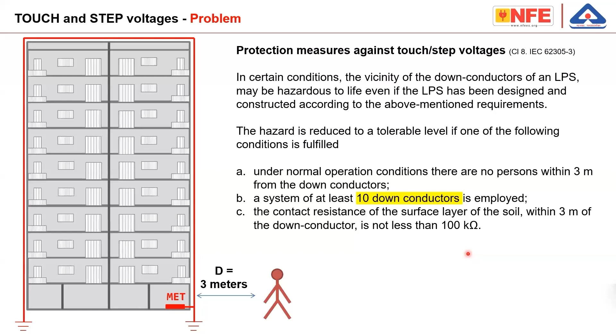Similarly, the step voltages are also mentioned in the standard. In order to avoid touch voltage, what you should do is this: the down conductor, where I am moving the cursor, of that part of the building up to, let us say, 2 or 3 meters, where a person may be touching, must be insulated. Insulation of exposed down conductors is provided giving a 100 kV, 1.2/50 microsecond impulse withstand voltage. Example, at least 3 millimeter cross-linked polyethylene. So if you are using a 3 millimeter XLPE cable for the last 3 meters, which is tested for a 100 kV impulse voltage, then the problem of touch voltage can be reduced.